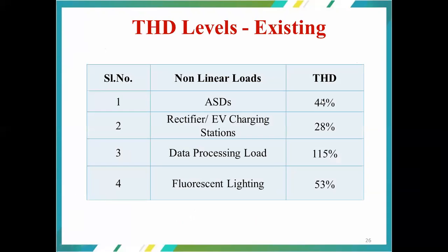So these are all the total harmonic distortion levels of the existing loads. If it is going to be an adjustable speed drive, wherein we are going to employ power converters or power electronic equipment at a wider capacity or in wider numbers, it is going to offer 44% THD. Rectifiers or EV charging stations give 28%, the data processing load 115%, and fluorescent lighting, that is electronic choke based lighting, 53%.